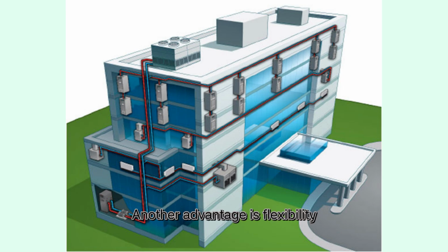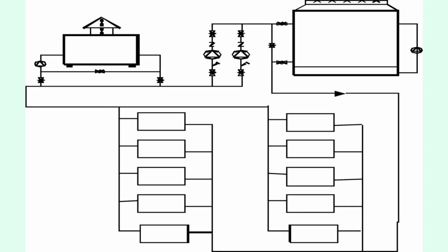Another advantage is flexibility. Closed-circuit towers can even be installed indoors, which helps maintain a cleaner loop and keeps the equipment out of sight. If an open tower is used instead, you must install an intermediate heat exchanger to isolate the tower water from the system loop. In that case, a high turbulent shell and tube exchanger is recommended because it's less prone to fouling and easier to service than a plate and frame type. Next, the boiler.